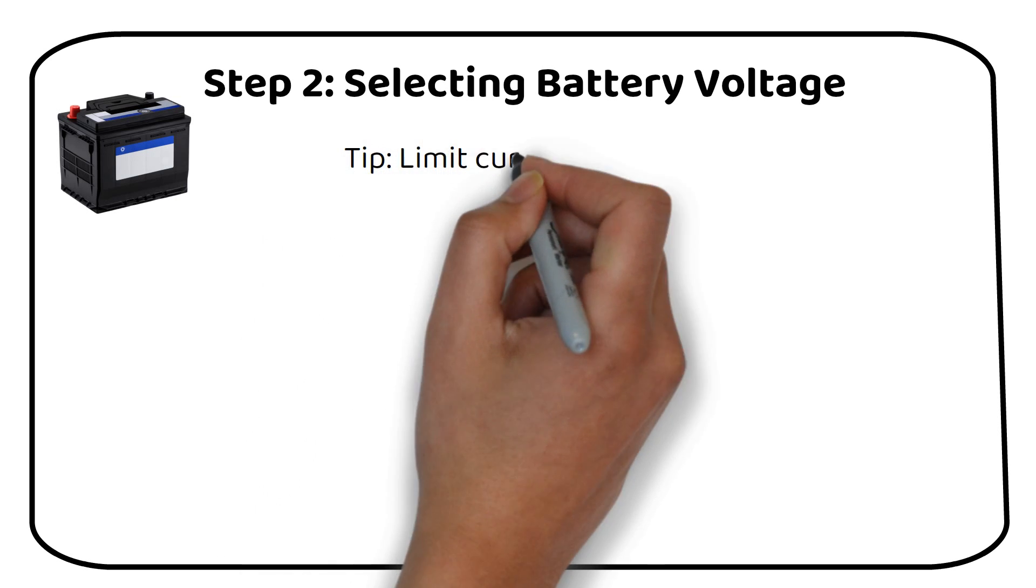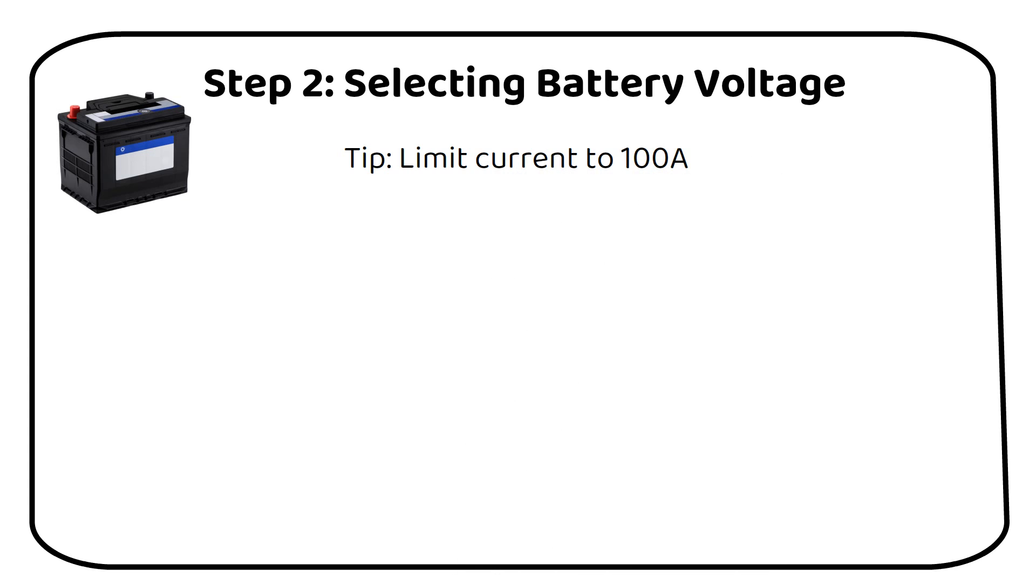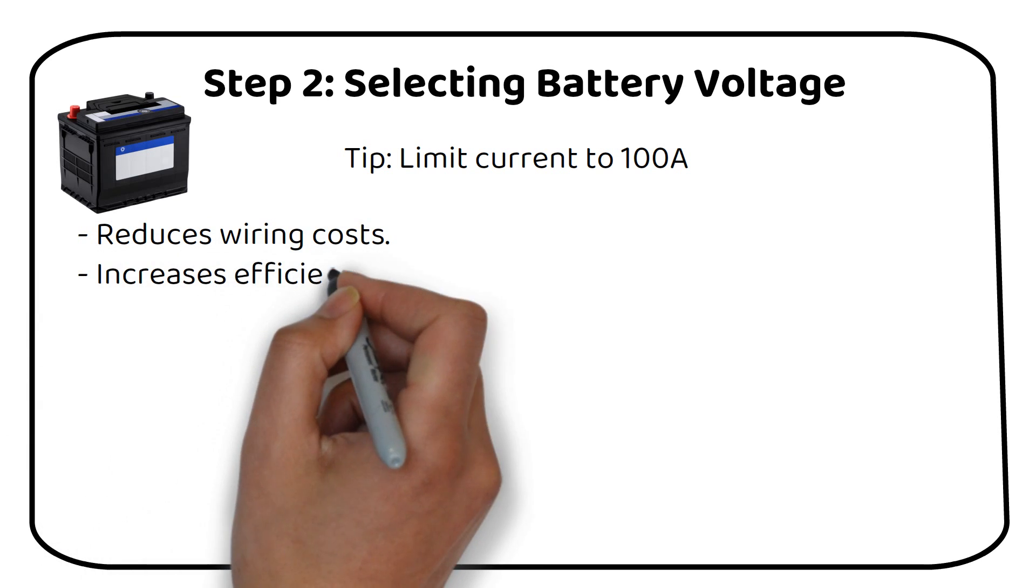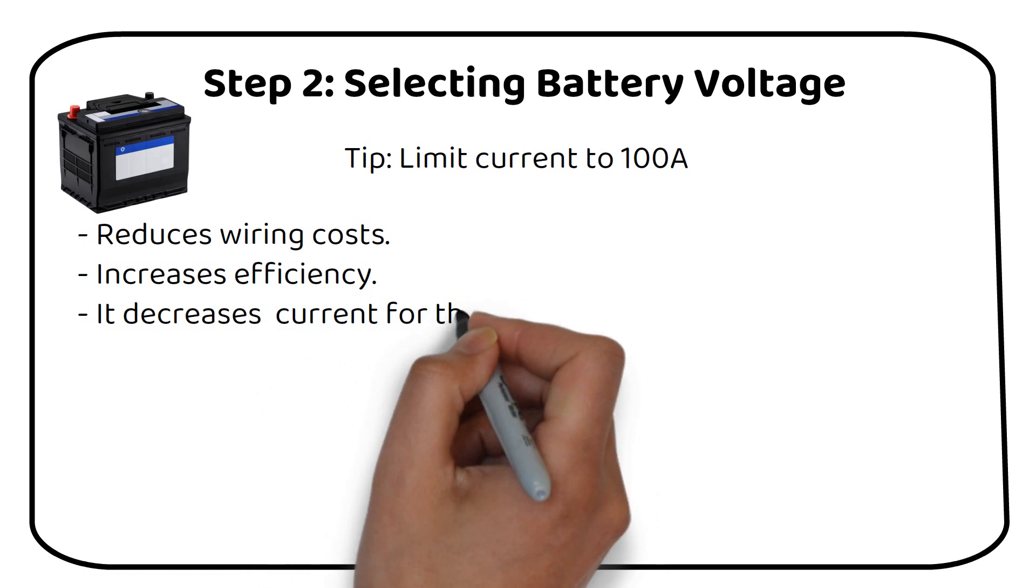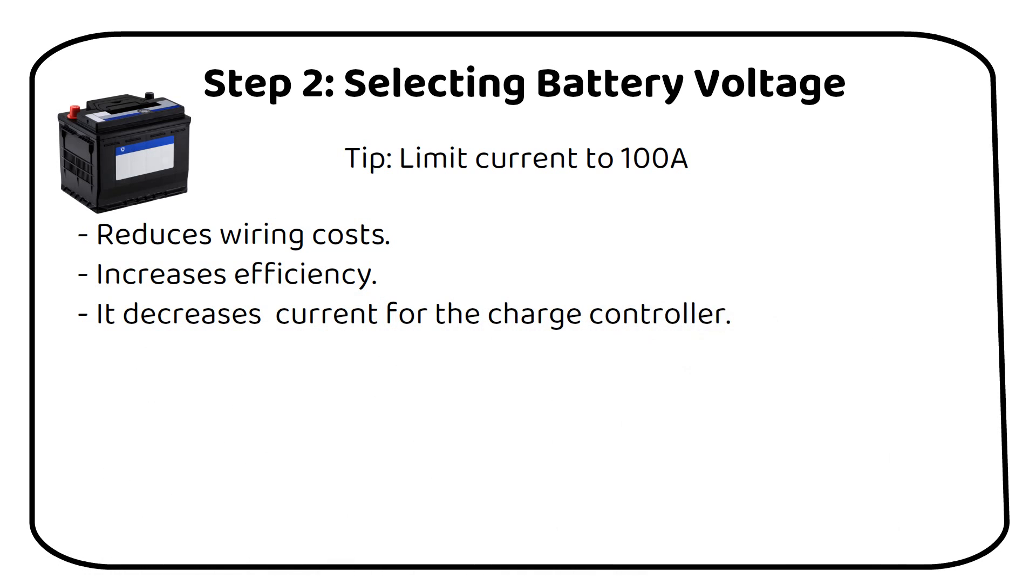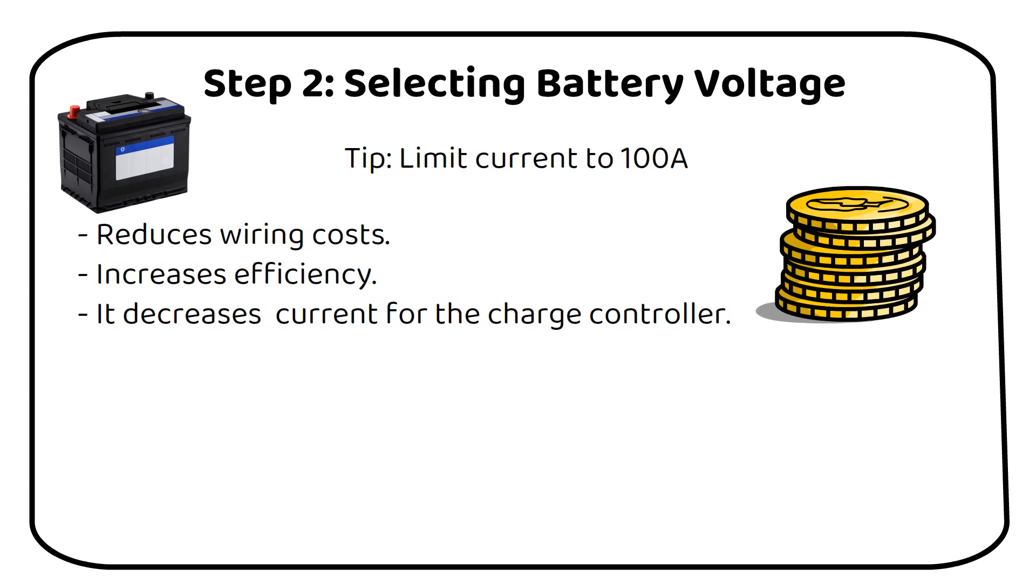Step 2. Selecting battery voltage. Choosing the right battery voltage is a critical decision in setting up your off-grid solar system. As I've discussed in previous videos, it's advisable to limit the current in your DIY off-grid system to 100 amps. Let's quickly recap why opting for a higher battery voltage is beneficial. It reduces wiring costs. It increases overall system efficiency. It decreases the current requirement for the charge controller. All these factors contribute to significant savings in your installation.